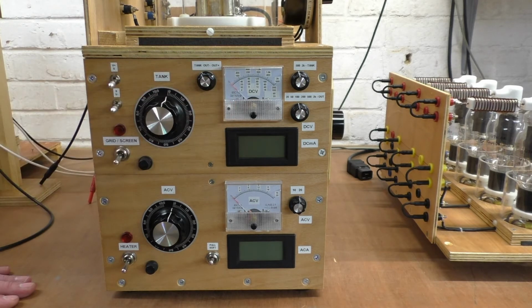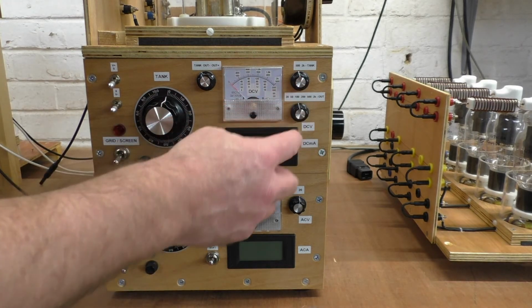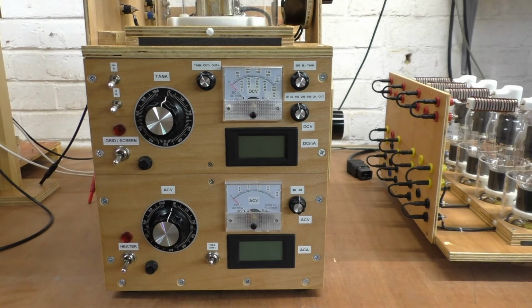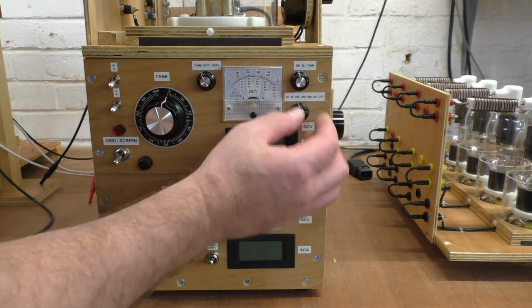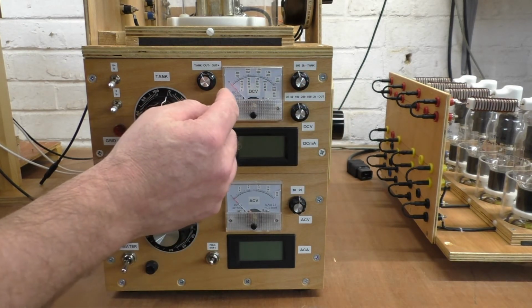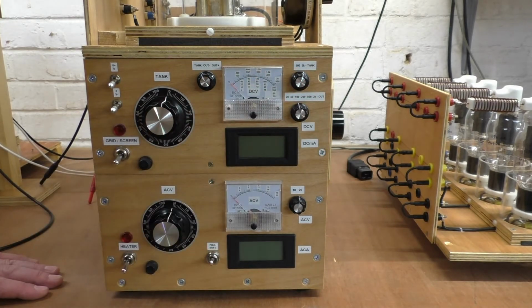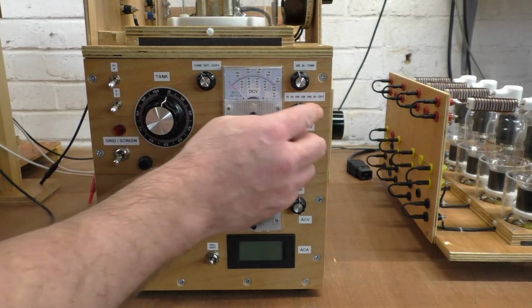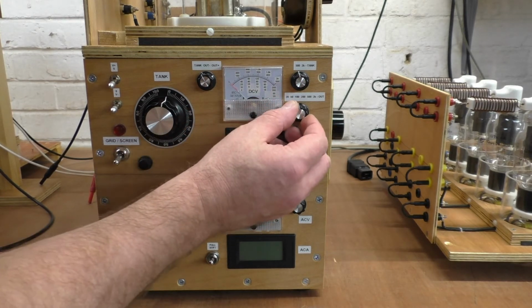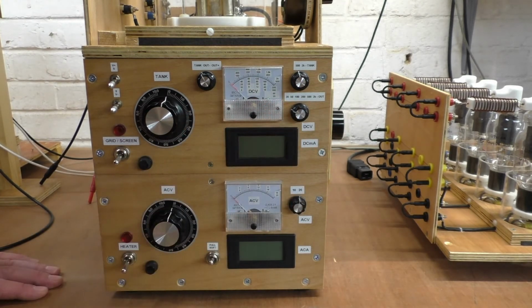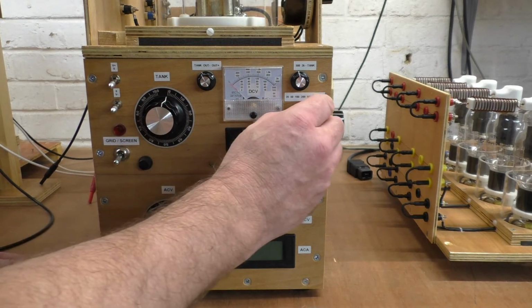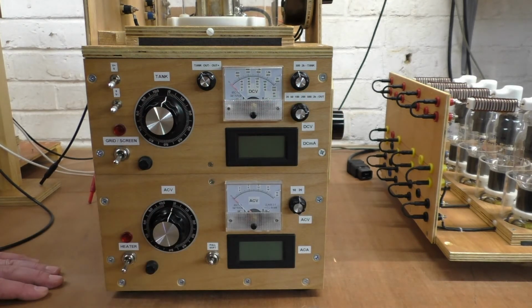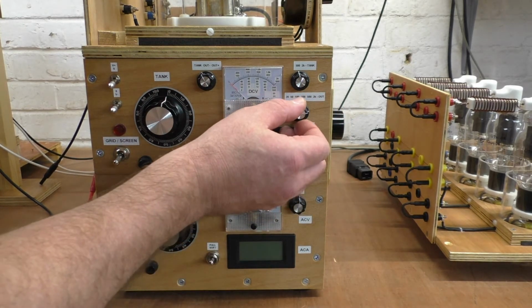And if we put it here, then we see what the output of the tank is. We can also scale the range. So for the tank, we can look at 500 volts and 2 kilovolts full scale deflection, and for the output we can set the resolution accurately down to 20 volts full scale, all the way over to 2 kilovolts.